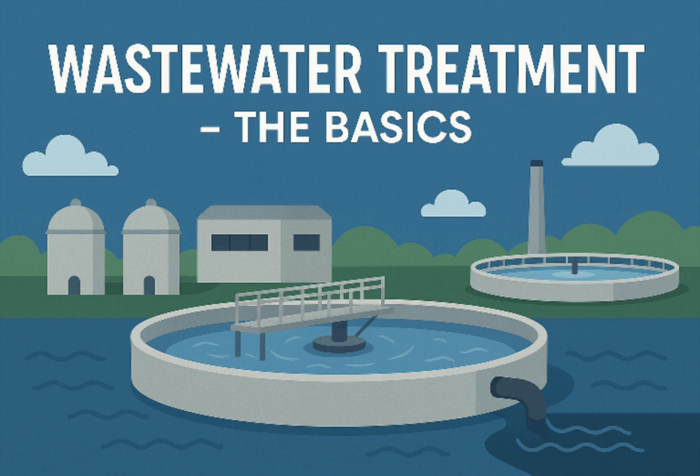What are the overall removal rates for secondary? Overall, secondary treatment typically removes about 85–90% of the BOD and suspended solids that were left after primary. And it's really effective against bacteria, removing 90–99% of coliforms. Impressive. But sometimes even that isn't the end of the line, is it? You mentioned optional steps. That's right. Some plants might add sand filtration after secondary settling just to polish the water even more, remove finer particles.